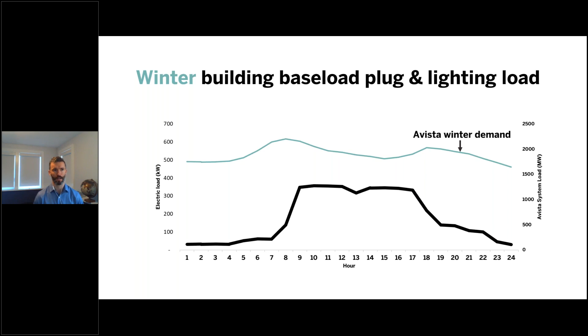So you can think about this load profile representing what we could achieve if we have a high efficiency building, but it was heated with a gas boiler. Next slide, please. In our case, we have an electrified heating plant. The electrification load is the biggest challenge for grid integration. This is represented here with the red curve. It's quite well correlated with the utility system peak. And the next slide, the resultant sum of these trends shows what is seen by the utility, and shows that we are requiring approximately 450 kilowatts of additional capacity to be built out in the utility system to support this development.